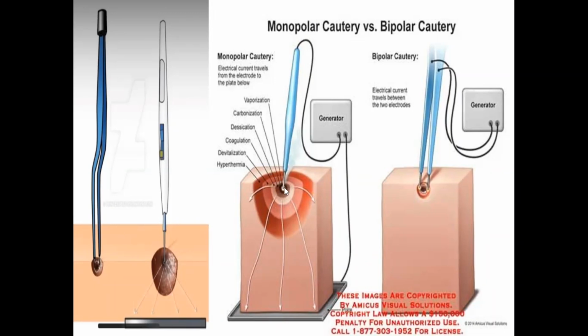You apply the heat, it causes tissue coagulation or cut, it causes vaporization, devitalization of tissue and goes through. It causes heat around the tissues and then passes through tissue to reach the plate. But in bipolar, electrical current travels between the two electrodes alone. It's localized at the site of use.